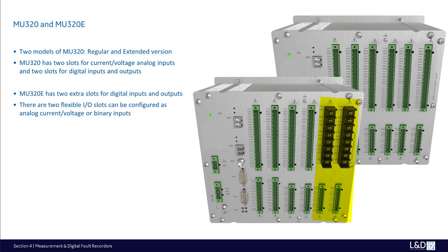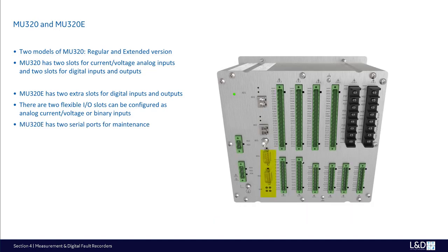There are 2 flexible I/O slots that can be configured as analog, current, voltage, or binary inputs. There's a maximum of 6 I/O slots that can be configured, allowing up to 96 binary inputs and up to 48 binary outputs. MU320E can be configured as a merging unit, remote I/O device, or PIU. MU320E has 2 serial ports for maintenance.